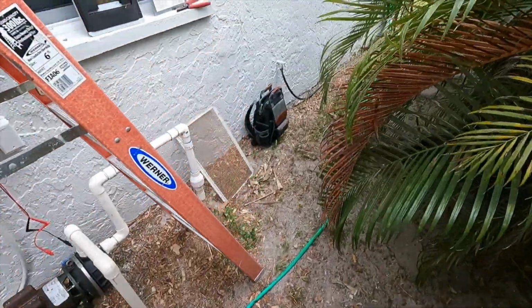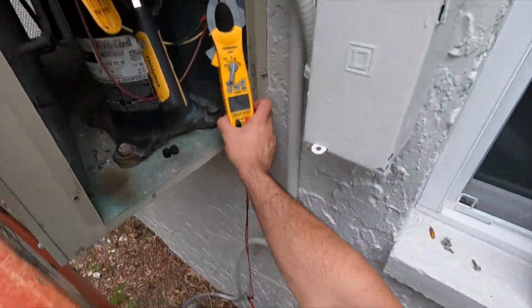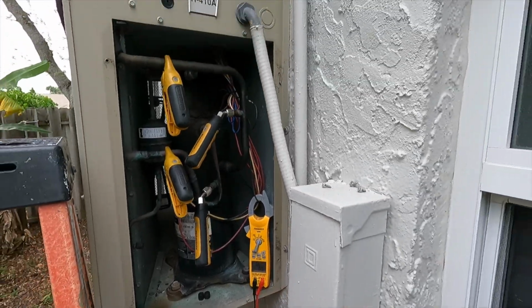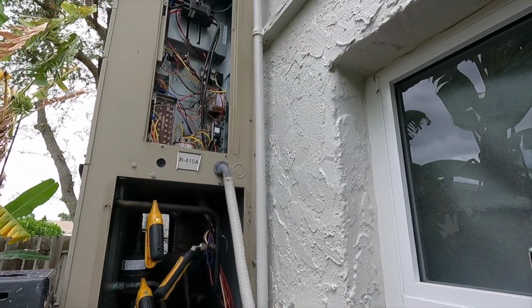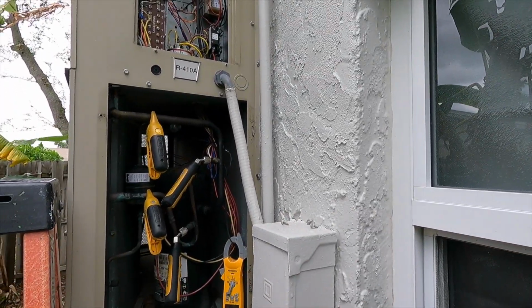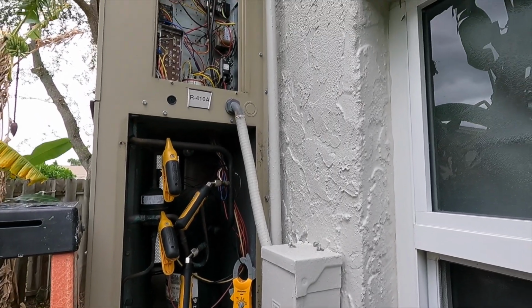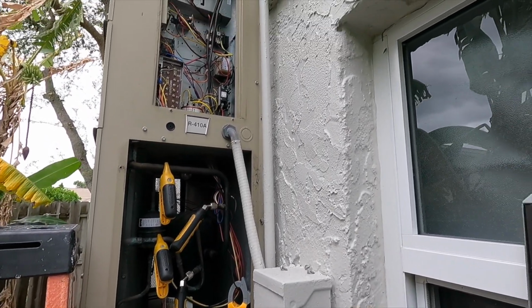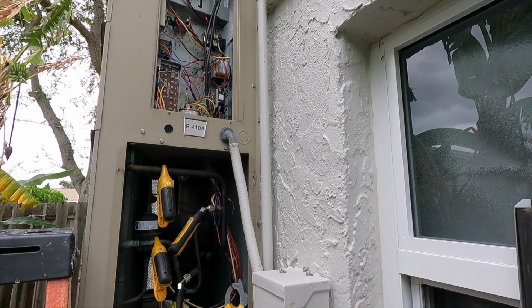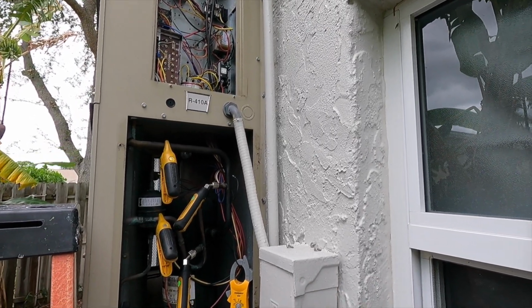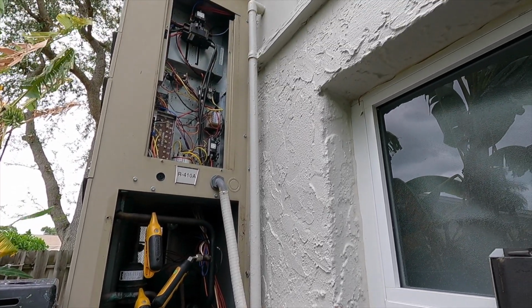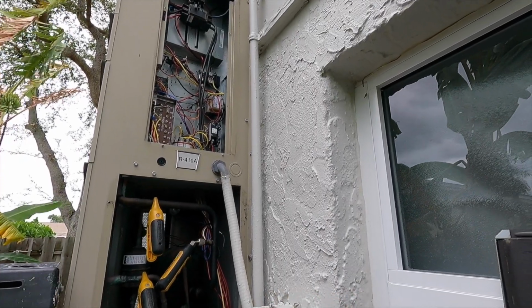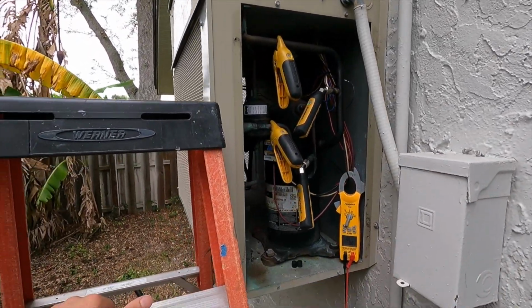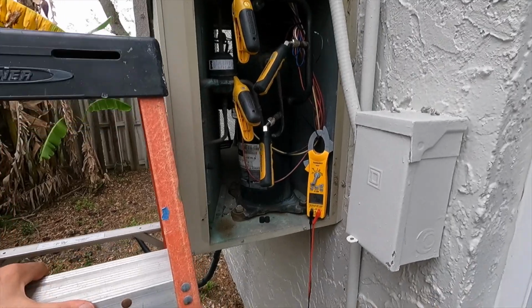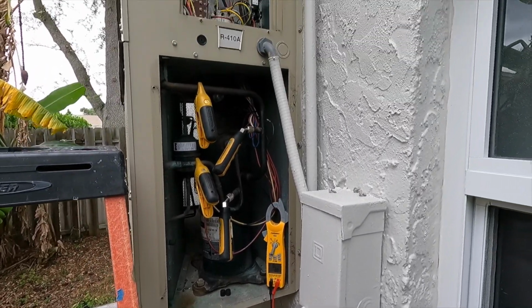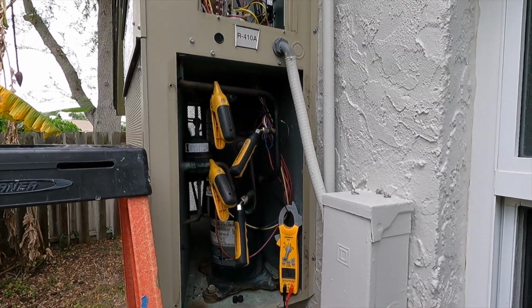All right, we got to start. Overload. So we got a high amp draw, higher than the meter can register. So no bueno for that compressor. I would at this point recommend a hard start kit for the compressor just to help with that initial kick. It also helps with the electric bill, and it will also extend the life of that compressor. So just like on another maintenance we did yesterday, a hard start kit would be recommended for this compressor.